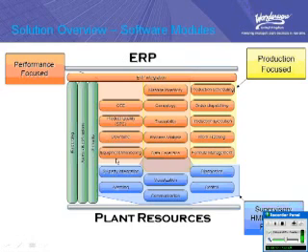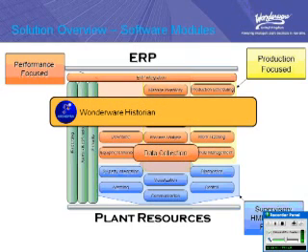Now, it's very important that we get data from our plant up to our business systems in order to enhance our process. And the best way of doing that is to collect your data from the plant floor and use it then for analysing your system. And within the Wonderware software suite, we have our Wonderware Historian. Now, this sits just above your lower systems, your diagnostics, your control, your HMIs, your SCADA systems, etc., collects the data and then makes it available to the business systems.